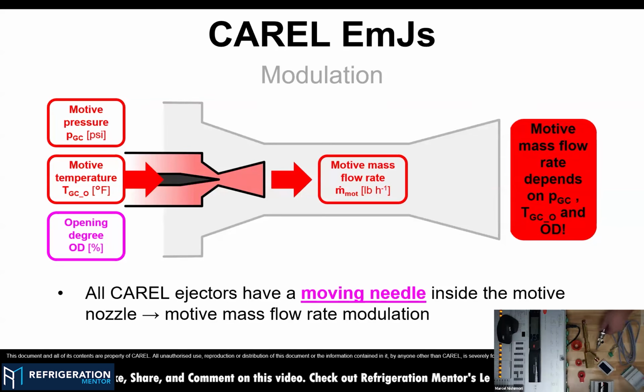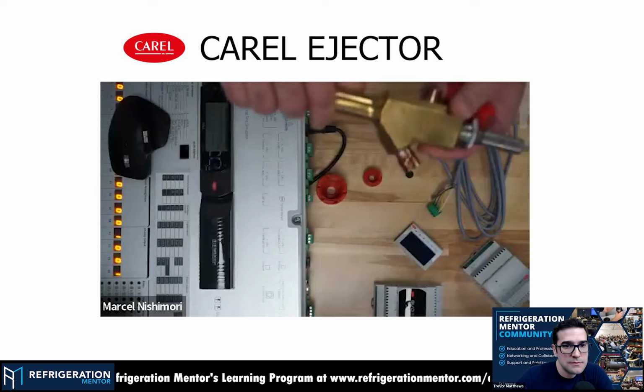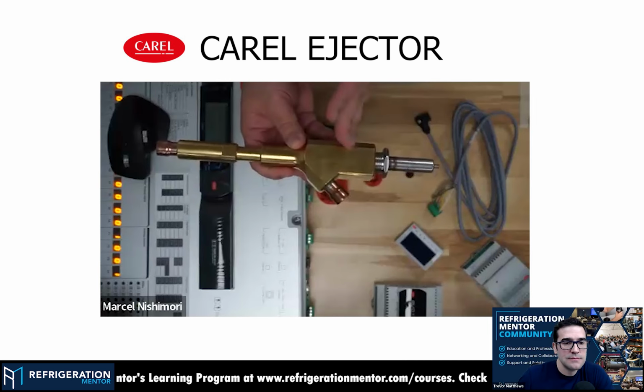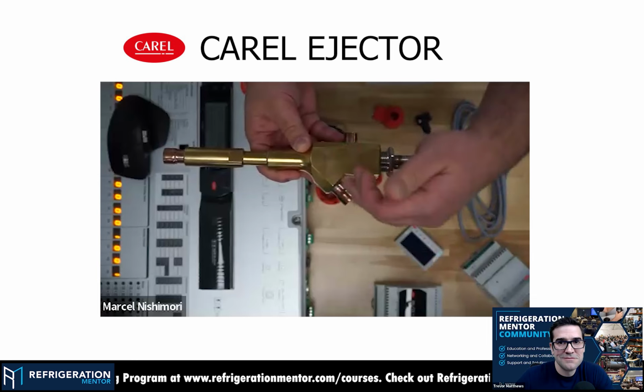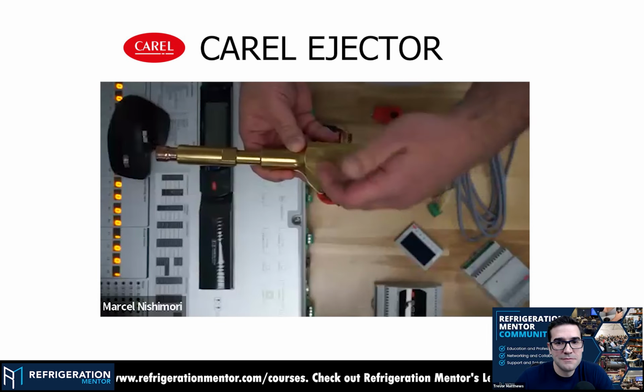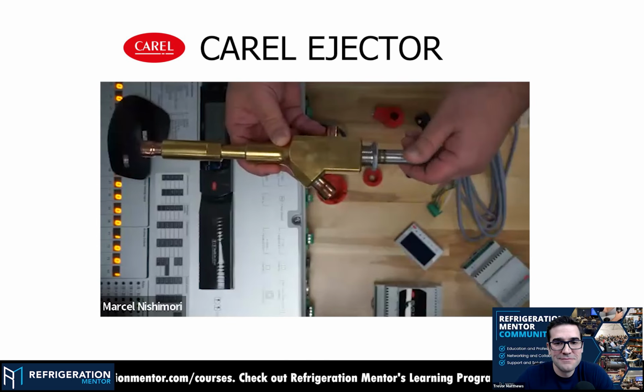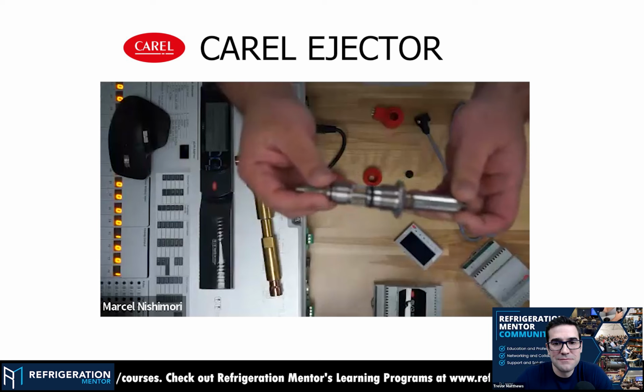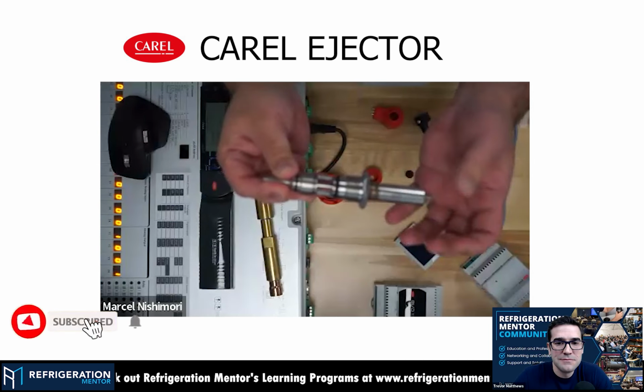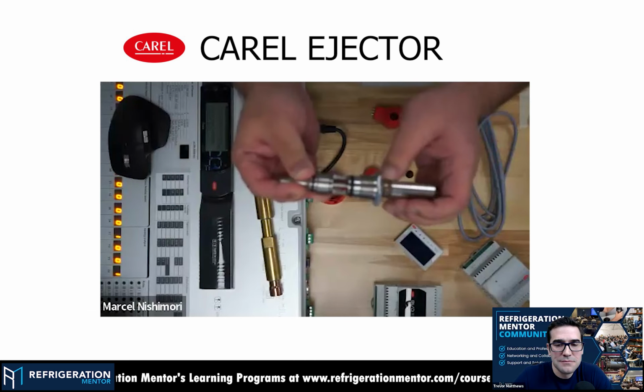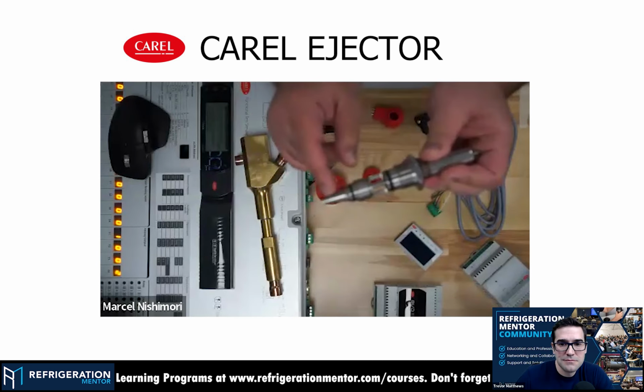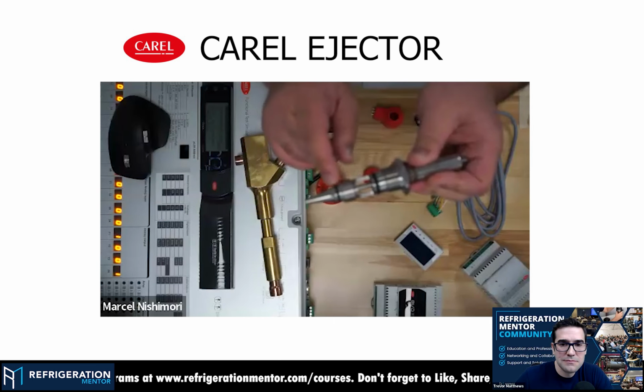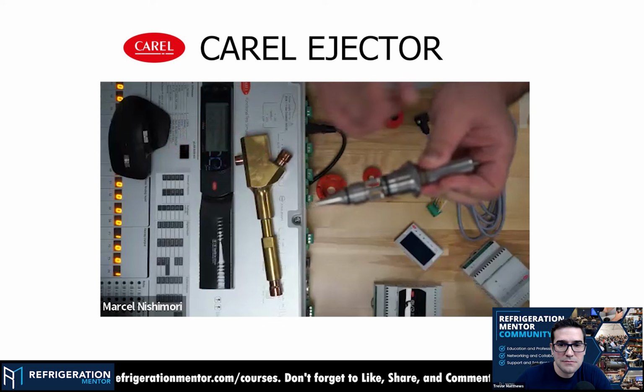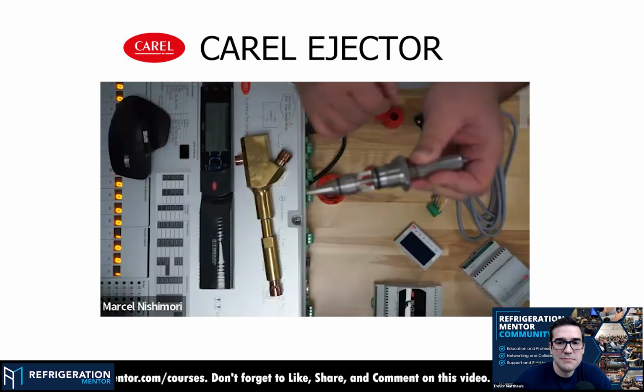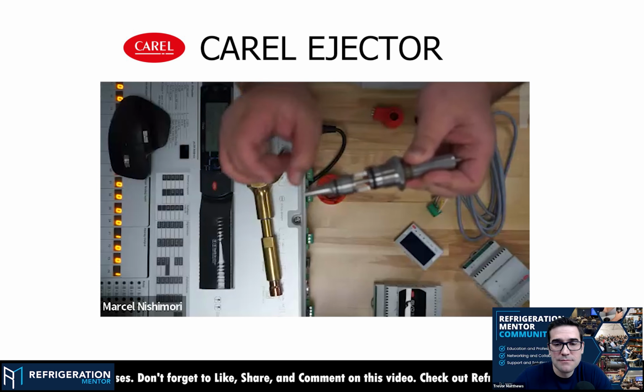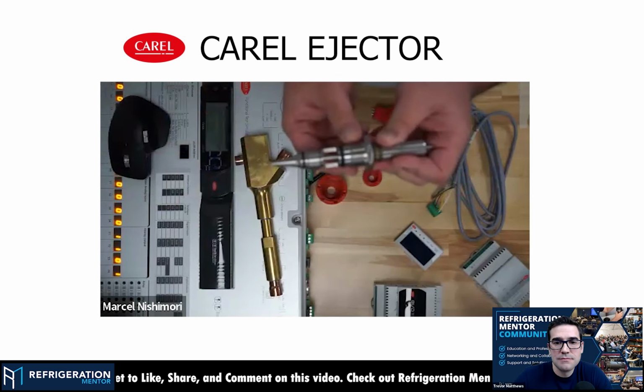Let me show you very quickly what we are talking about. So this is the ejector of CAREL, okay? We have our body. The gas cooler flow comes from this direction, and we have the suction coming from this direction. If you see, the geometry of the ejector also allows the suction from MT to be more fluid inside the ejector. And here is what we call our cartridge, and it works with the same principle as a bipolar drive. In fact, this motor is like a bipolar that CAREL manufactures. And here you can see that I have the needle, and the needle is controlling the amount of refrigerant flow that can pass through the ejector. So this needle can go up and down and make sure that we have the precise refrigerant flow that we need for that specific application. And this is what it is controlling. And the ejector will take effect from this part, from the suction line.